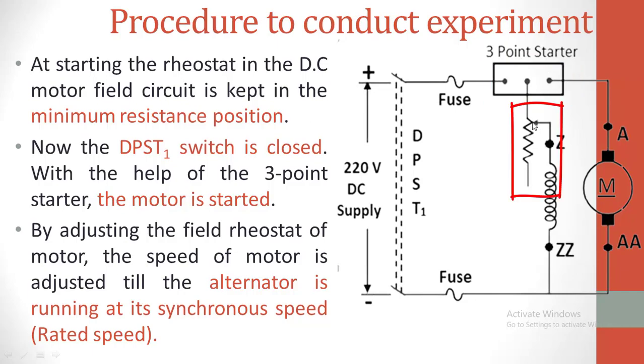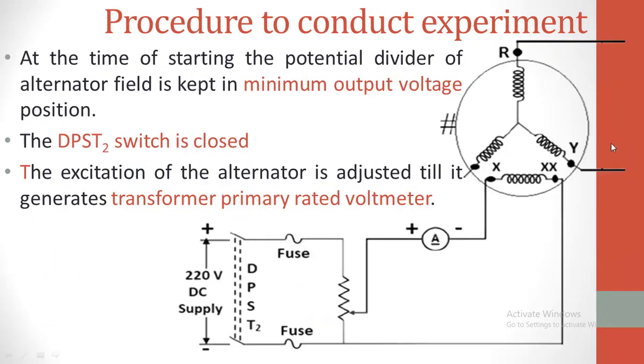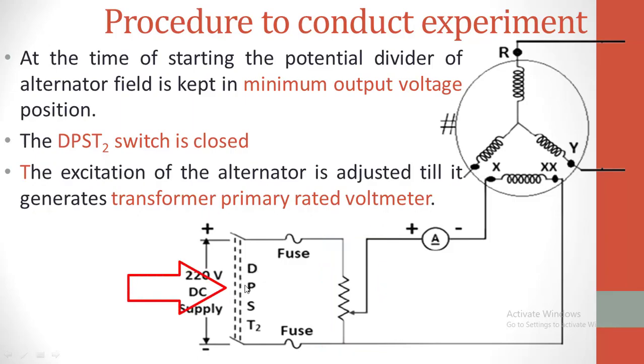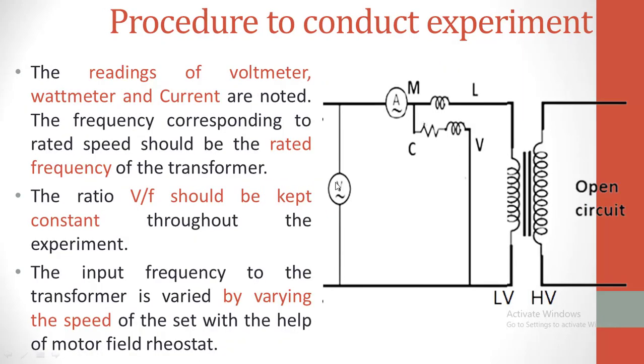By adjusting the field rheostat, the speed of the motor is adjusted such that the synchronous generator rotates at synchronous speed. For the synchronous generator, at the time of starting, the potential divider in the field circuit is kept in the minimum voltage position. The DPST switch is closed. We adjust the excitation until the generator generates the rated voltage of the transformer. The readings of voltmeter, wattmeter, and ammeter are noted.